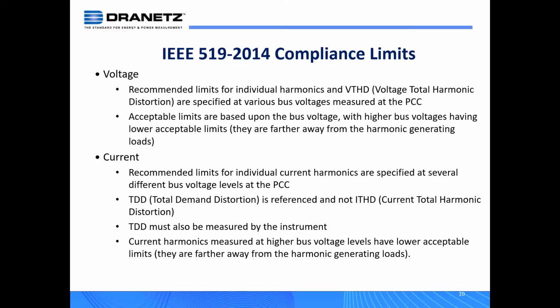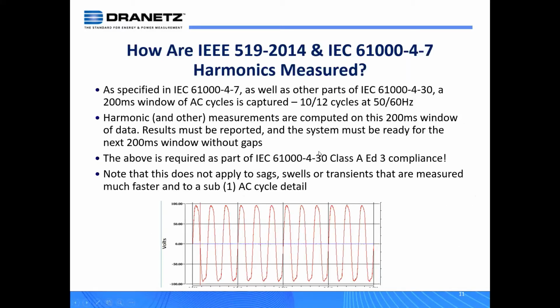And that's the basis behind TDD. But again, voltage and current references are used based upon the bus voltage. And that's the big thing. So how are these measured by the instruments? This is important because, and I don't want to get too technical here, it goes into the ability of your instruments to produce this data. And that's why older instruments can't measure to these standards, because they don't have the computational requirements that are needed for 61000-4-7 and of course 519-2014.